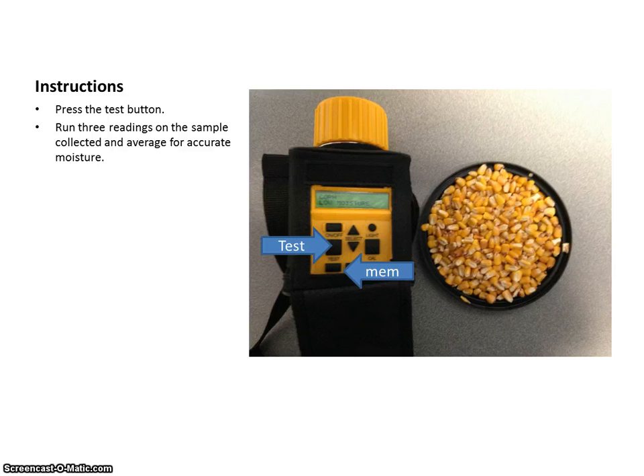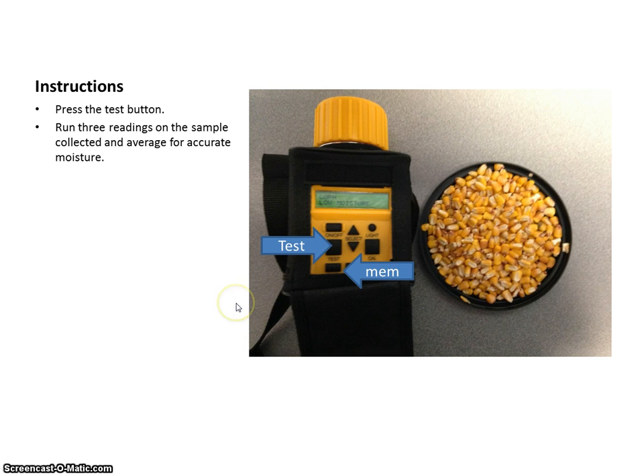Then you push the test button. The unit will take a few seconds to run the test, and it'll come up and tell you what the moisture, temperature, et cetera, is of the grain, and then you'll want to hit the memory button to store that. It's a good idea when you're taking moisture to run at least three samples to get a good average for an accurate moisture.